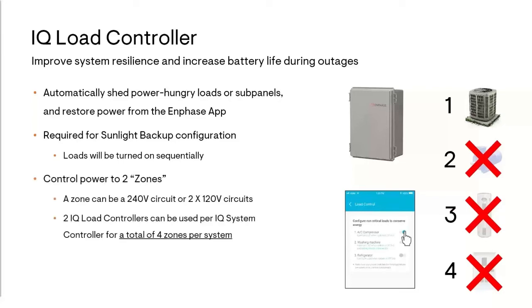Each load controller can control power to two zones. A zone can be either a 240 volt circuit or two 120 volt circuits. Two IQ load controllers can be installed per system for a total of 4 zones. For most sunlight backup systems, 2 load controllers should be included to control all 4 zones. But if the design only calls for two essential loads or zones, then just a single IQ load controller could be used.